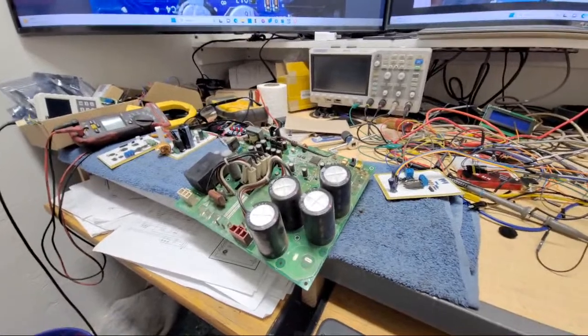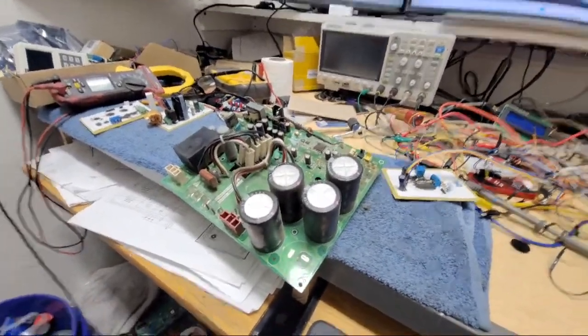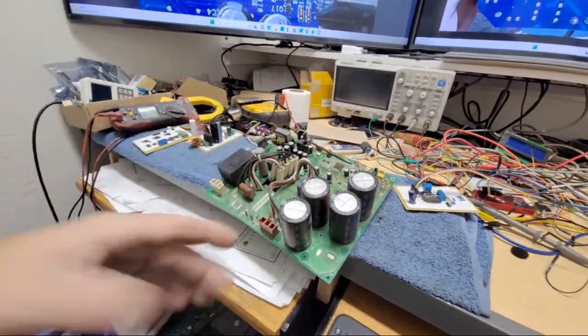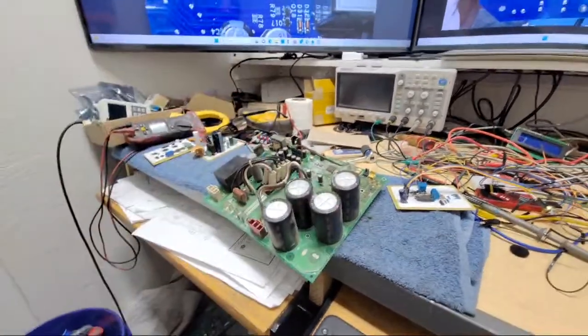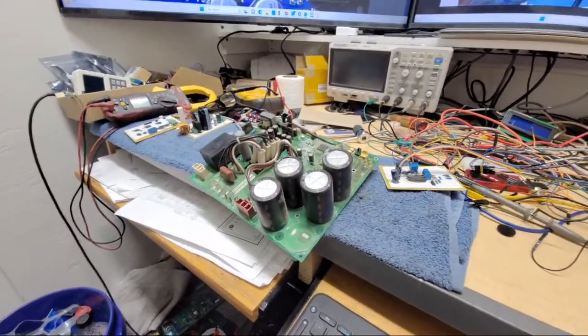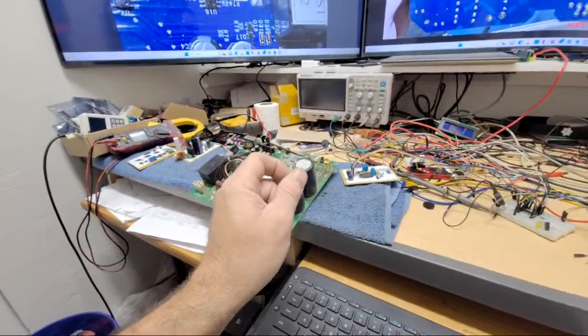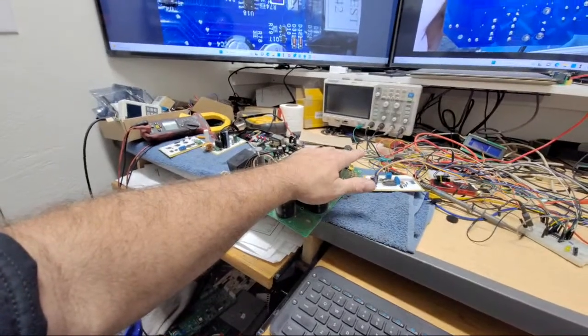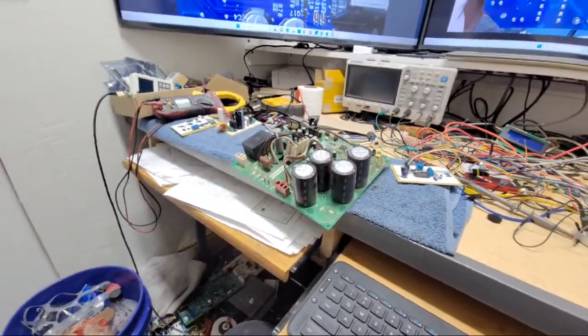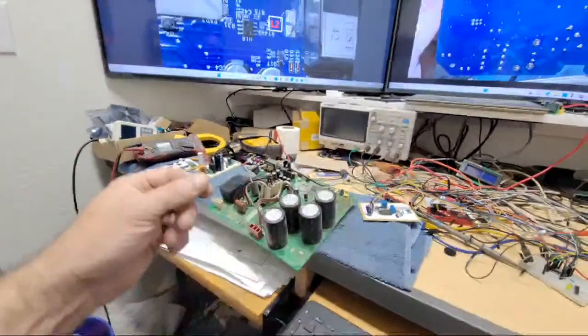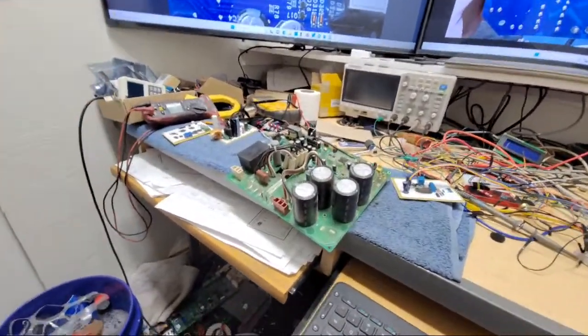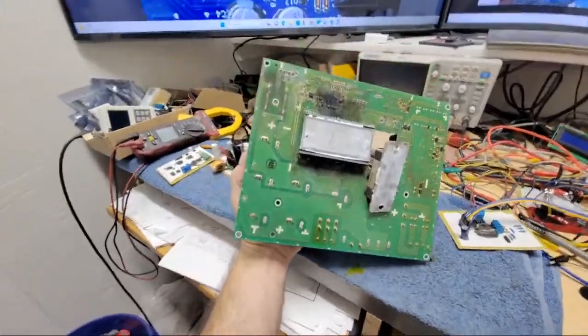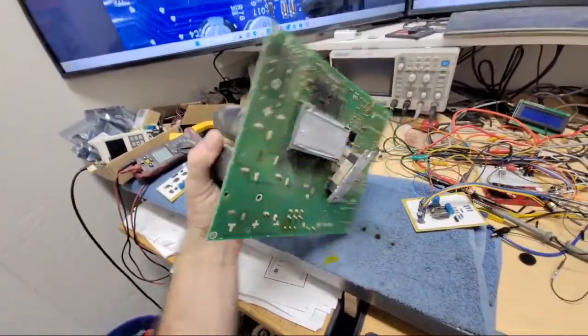You also vary the frequency between the plus minus inversions, and then you have a variable frequency drive. So when you look at a variable frequency drive's curve, it's just less pulse widths, so it's an RMS thing. The voltage is always fully applied, whatever that voltage is of the unit—it's never actually lowering the voltage. It's just the RMS measured less because the pulse widths are shorter when it's first starting off, and then it brings up the pulse widths at the same time. It's also speeding up the motor, because you have to have the torque against the same load. So you'd have to have components for that.